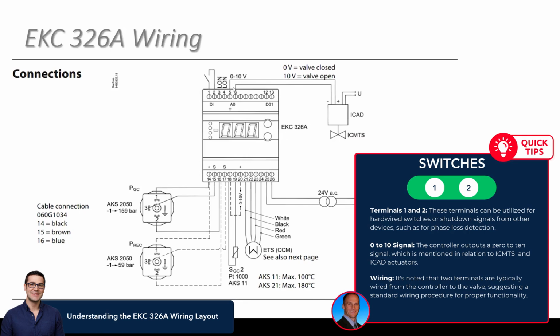Then you get into more of the main settings or terminals that are related to the controls. The 0 to 10 that we've mentioned for the ICMTS, which that's the valve and ICAD. We'll get into a little bit here too. That's the actuator that goes on top of the ICMTS that actually receives the 0 to 10 from the EKC. That's 2 terminals that you're going to be wiring to just about every time to come out of that controller into that valve.